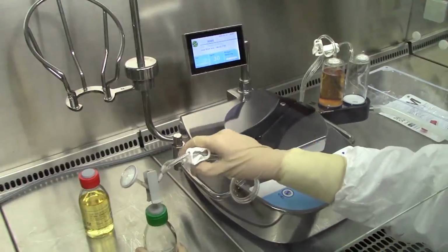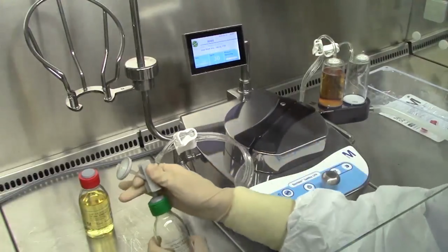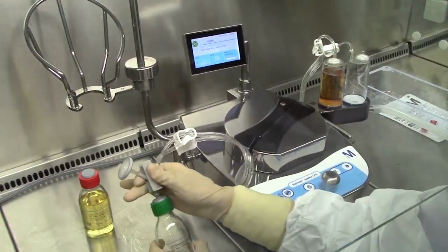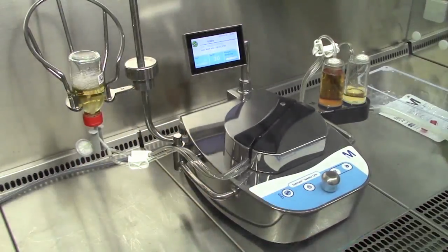Repeat the media filling step with a thioglycolate bottle on the second canister after clamping off the opposite tubing line so that the remaining empty canister can be filled with thioglycolate. Note that for thioglycolate, fill-in is done at a low speed, maximum 30, to ensure the aeration is minimal and media returns as quickly as possible to its double layer state.